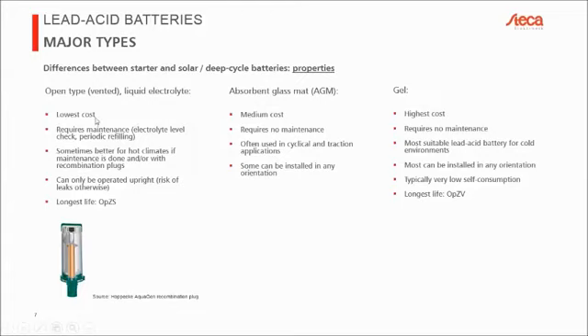The first type, open liquid electrolyte, is typically the cheapest. It requires some maintenance, so you need to refill it from time to time with water. It's sometimes better for hot climates, simply because these will actually evaporate the most water out of all three types, but they have the advantage that at least you can refill them.